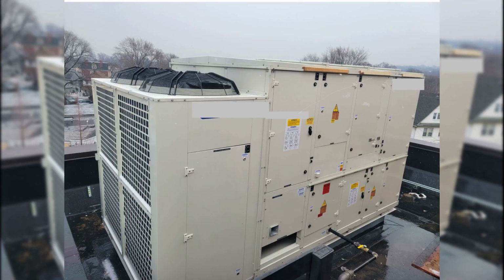9. Ventilation. Energy recovery wheels, ERW, and demand-controlled ventilation are generally required for all custom RTU units. There are specific exceptions, but they require approval from the authority's TSS unit and must be justified with energy modeling. 10. Perimeter heating. For spaces served by central DX MZVAV heat pumps, electric baseboard units are required for perimeter heating in non-assembly areas like classrooms and offices.